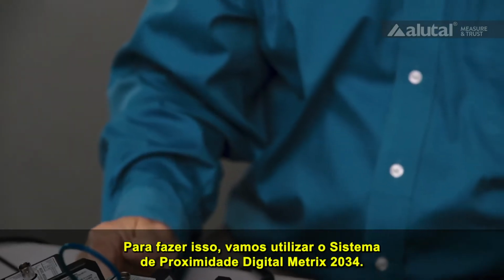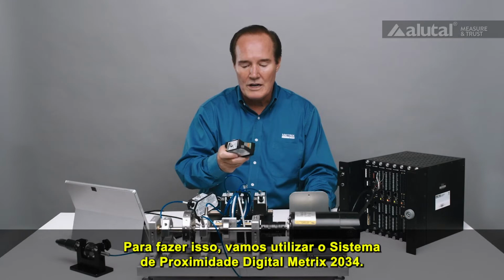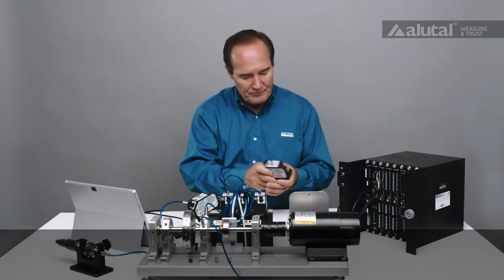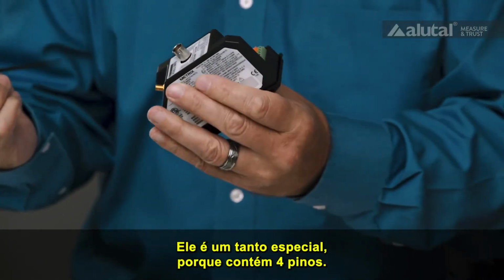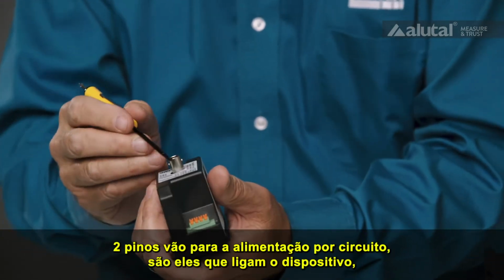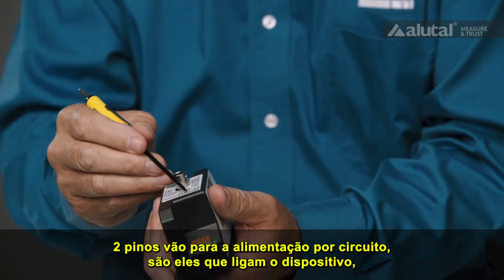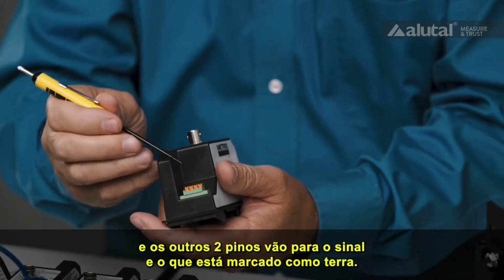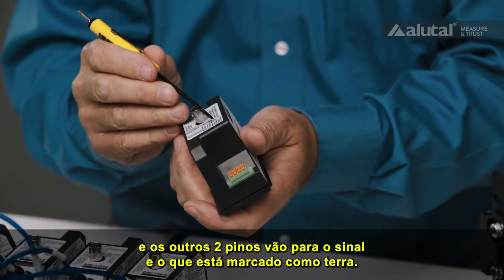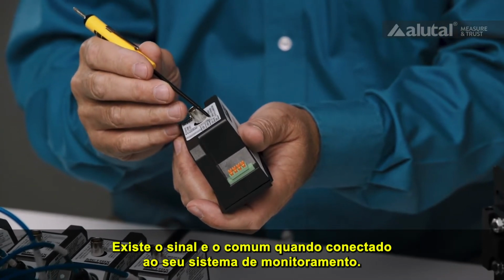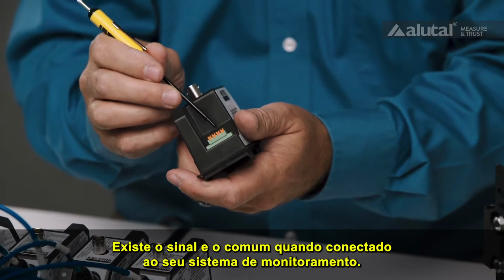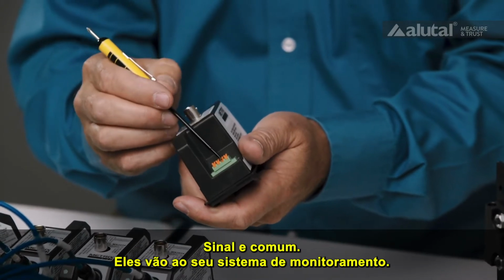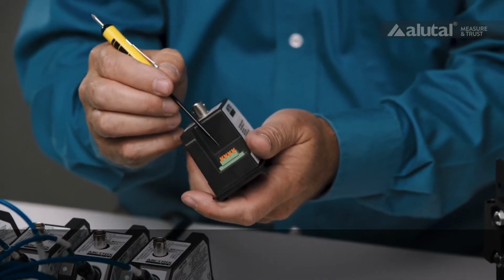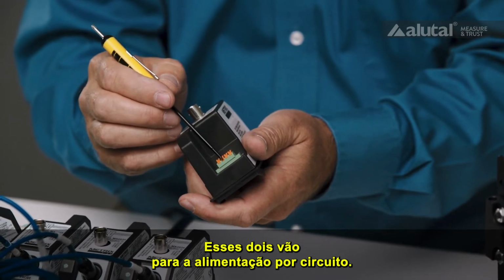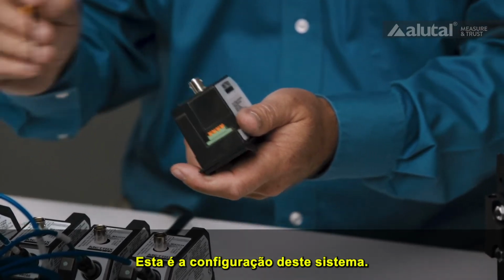And to do that, we're going to use the Metrix 2034 digital proximity system. Well, this is kind of special in that it has 4 pins. Right? 2 pins go to loop power, and that's what powers the device. And then the other 2 pins go to signal and what I have marked here as ground. There's signal and common when it goes to your monitoring system. So signal and common, that goes to your monitoring system. These 2 go to your loop power. So that's how I've got this system set up.